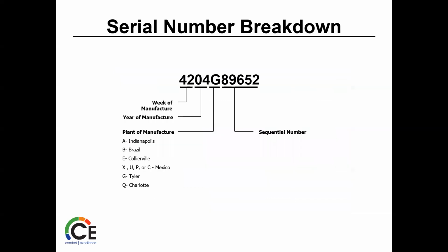Serial number breakdowns. You know, again, this is important mainly for us. One, it's going to tell us how old it is, or at least when it was made. You know, sometimes even though it's an 04, it may not have been put in until 05 or 06, and that's fine. We can verify that. You know, as far as Carrier goes, they're looking at which plant did it come from, especially with issues. So they love to have that.